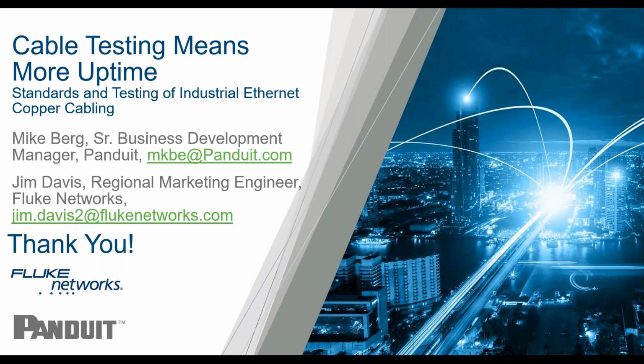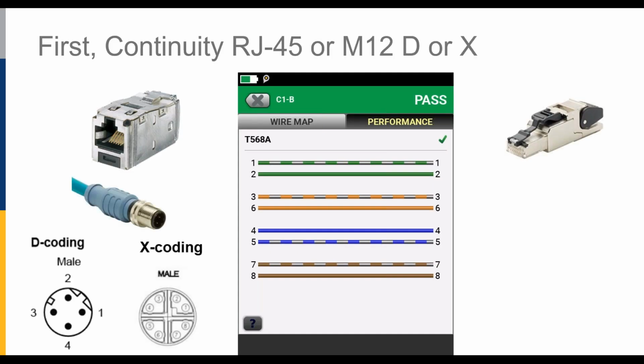Okay, so Jim actually addressed that a little bit in the presentation where he was showing you the newer device with the 4 pairs, which is the X code, and then the D code, which actually uses 2 pairs. So you're going to find the D code has been out there a little bit longer — those are going to be connections made to your smart blocks or smart modules with a D code type connection. And what you're going to find with the X code are more of your processor-based connections, your wireless access points, RFID systems. Some of the switches are based in this format as well, so it's kind of an emerging technology, the X code, using the 4-pair connection. Performance levels: D code is usually 10/100 and category 5E, and the X code is usually Cat 6A and gigabit performance.